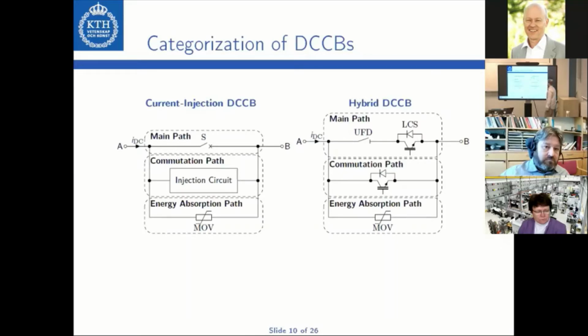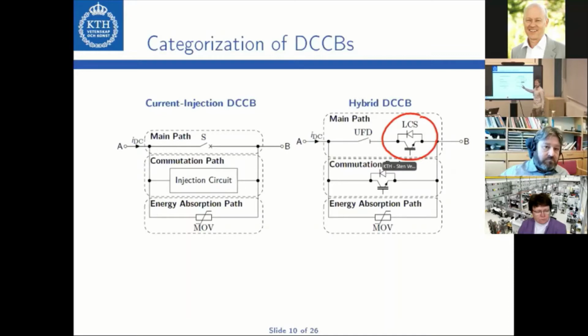The hybrid DCCB, on the other hand, uses power semiconductors to operate. The main path consists of an ultra-fast disconnector switch and an LCS, load commutation switch. This is a power semiconductor rated for only a fraction of the line voltage. The commutation path also consists of power semiconductors. This is now a high voltage power semiconductor valve, which means that hundreds of power semiconductors are connected in series. Thus, the commutation path is somewhat like a solid state breaker. The current is then commutated from the main path to the commutation path by turning off the LCS and turning on the semiconductors in the commutation path.